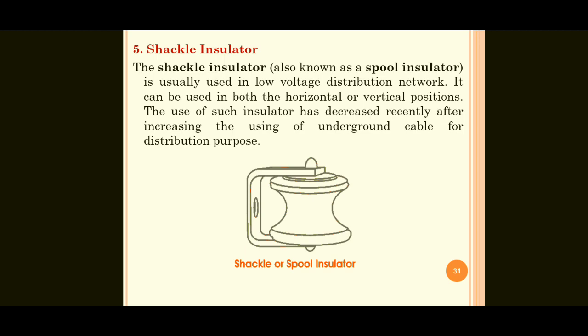So next one, strain insulator. These are used at the dead end of the transmission line to overcome the tension at the end of the line. So the first three types are used in high voltage applications. Stay insulator and shackle insulators are used on the low voltage side. These shackle insulators are placed either in horizontal or vertical position.